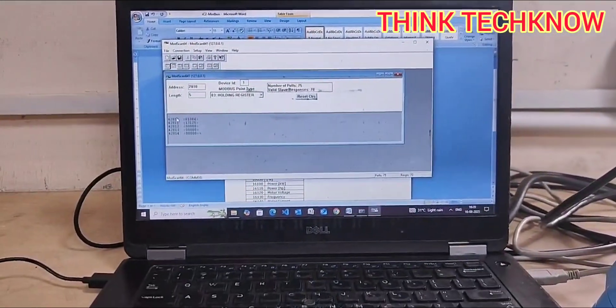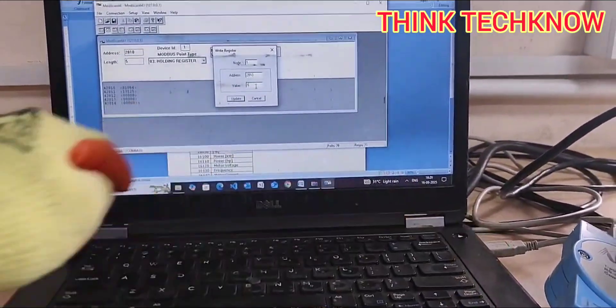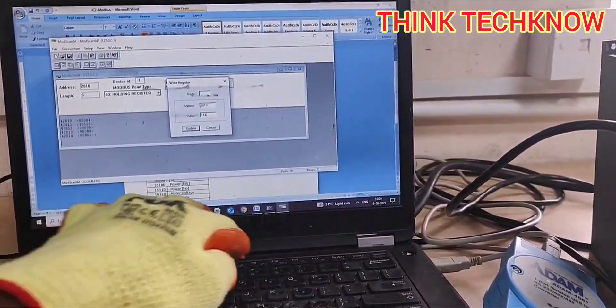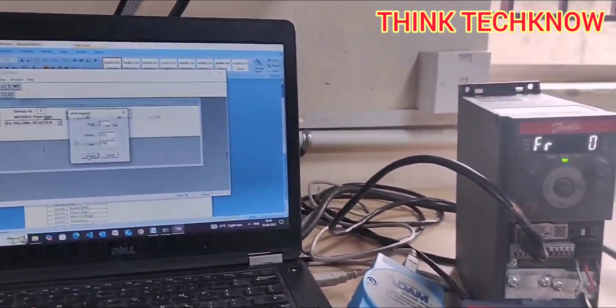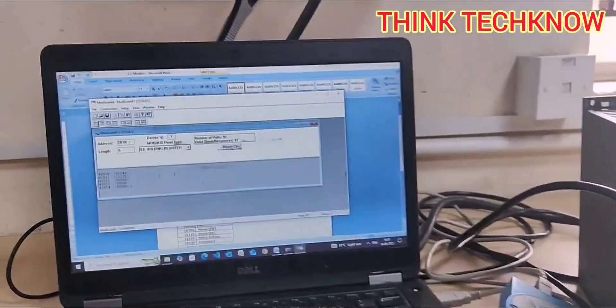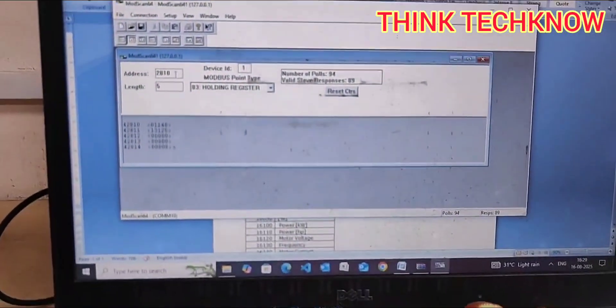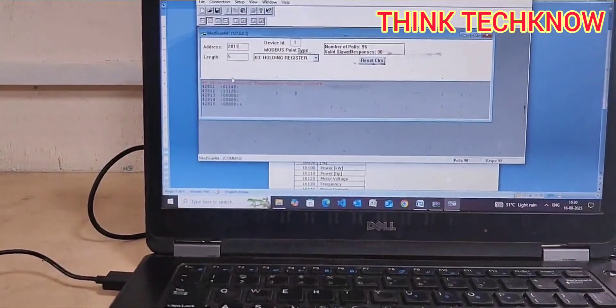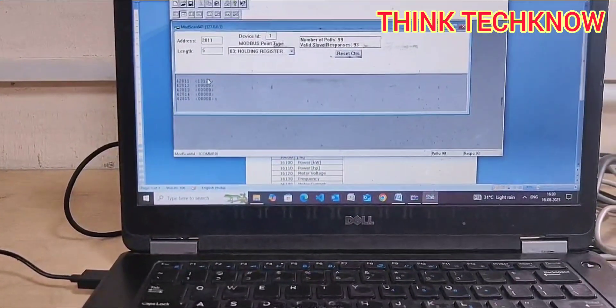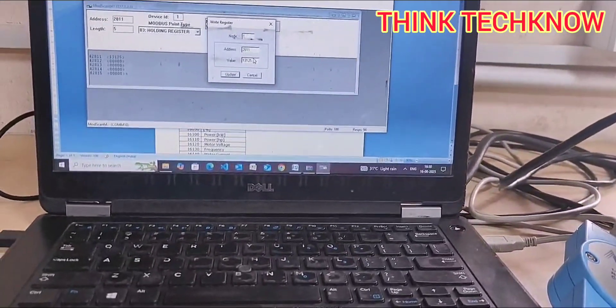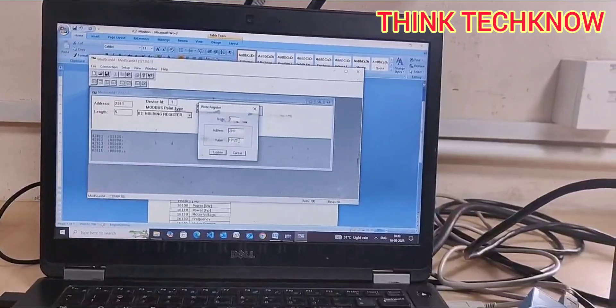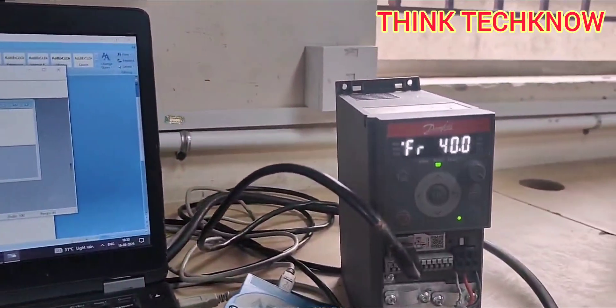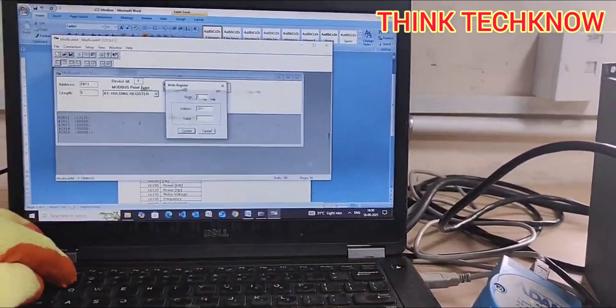IC2 VFD through Modscan. Now I am going to change the reference value. For that, we need to start the VFD, so I am giving 1148. If I give update, it was started. You need to enter address 2811 here for feeding reference. 2811 is the concern address for feeding the reference. Inside 2811, you can enter integer values. Zero is for zero hertz, and 16384 is for 50 hertz.